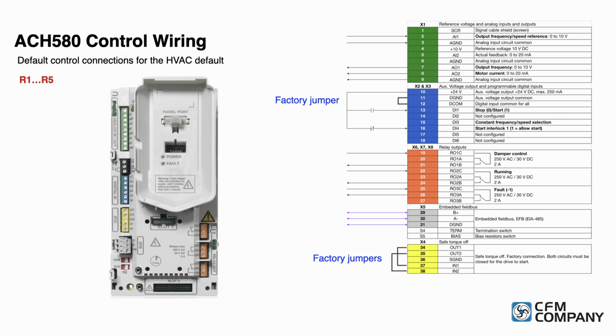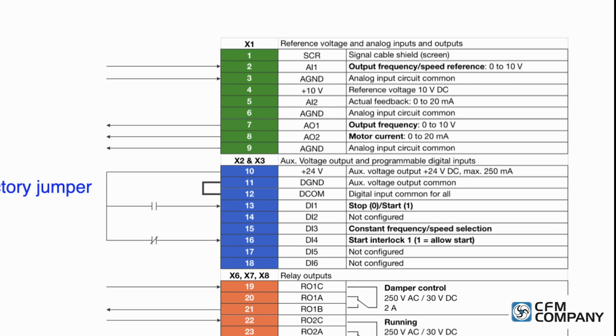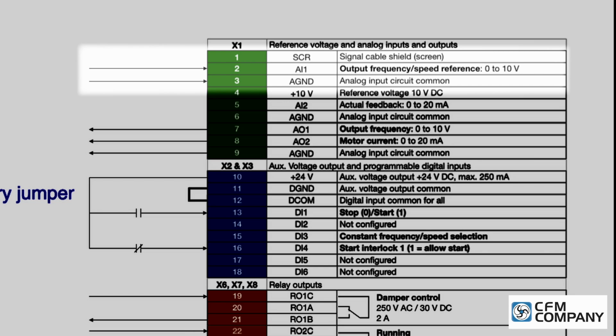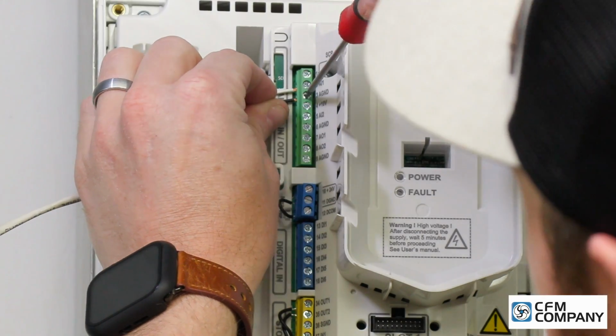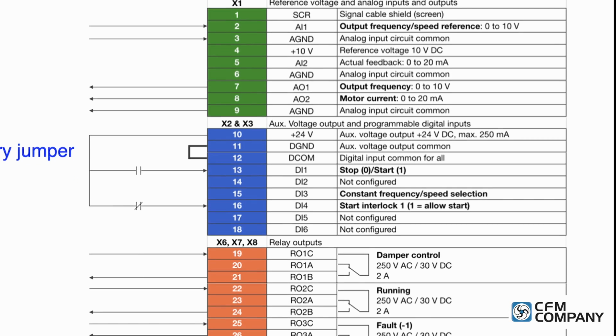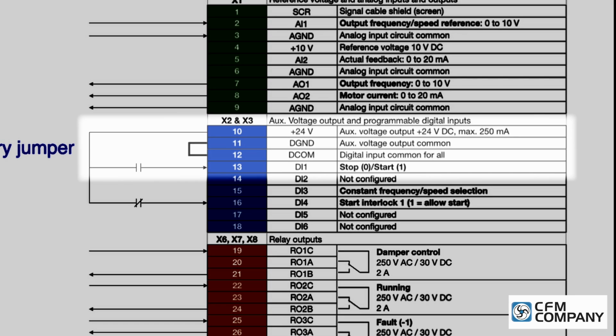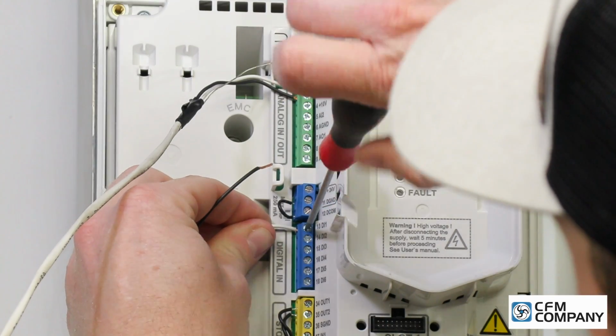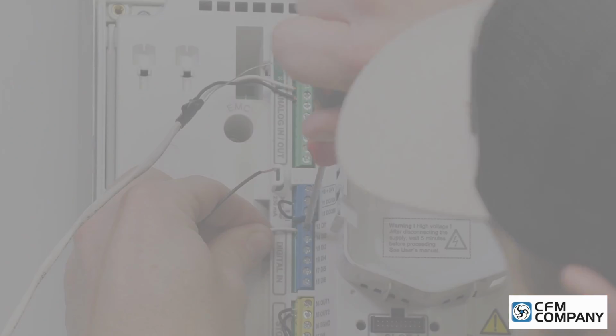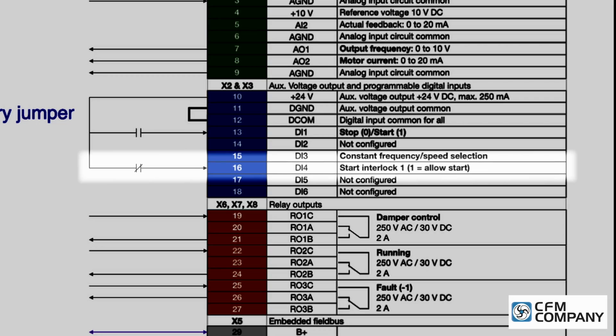Not shown in this video, many of the original field control wires were spliced and extended to reach up to the new ACH580 drive terminals. Starting at the top, the frequency reference is connected to the analog input 1, terminals 2 and 3. The start-stop command is connected between the 24 volts DC, terminal 10, and digital input 1, terminal 13. The start interlock 1 is connected between the 24 volts DC, terminal 10, and digital input 4, terminal 16.